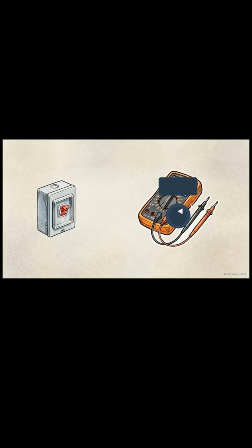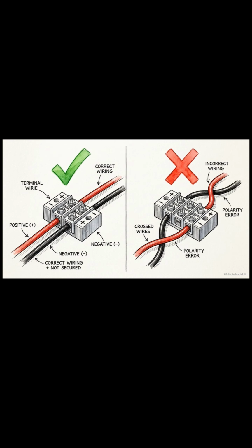You will set your digital multimeter to DC voltage and probe the input terminals at the DCDB. You are looking for a steady, positive voltage reading. If that reading shows a negative number, your polarity is reversed. You have crossed the positive and negative wires. You have to fix this immediately, or you will destroy the inverter the moment you power it on.